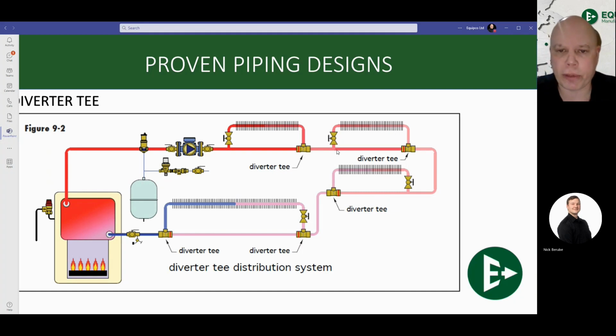This is called your monoflow or one directional tee, where that resistance creates your flow. And we still have the same problems happening in these guys here, where the temperature gets cooler and cooler as you go on. Also, it's getting harder and harder to find diverter tees. As far as I know, there's only 2 manufacturers of the diverter tees or monoflow tees out there right now, and that's B&G and Taco. There might be more, but if you find yourself in a pinch, those are the first 2 companies that I would call to find these monoflow tees.